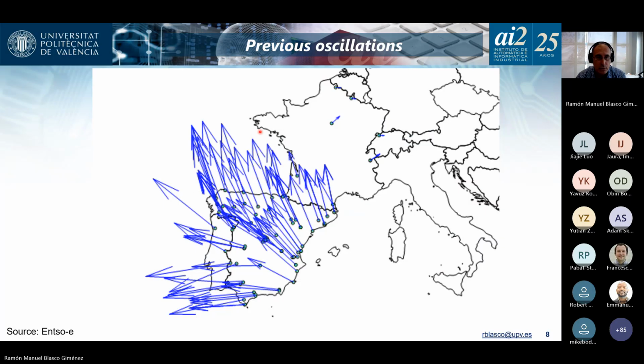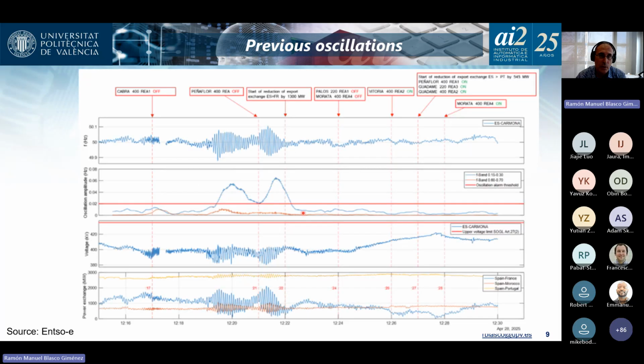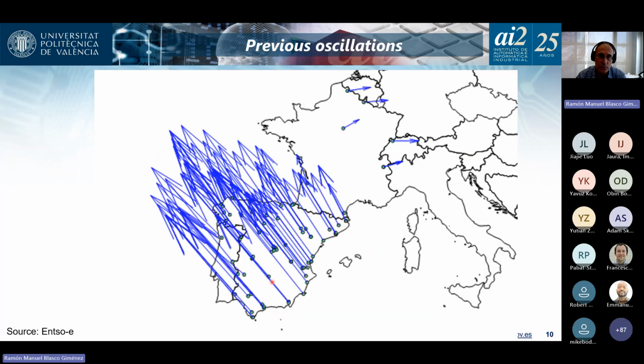If you see these oscillations, the 0.6 hertz, clearly the generators in the north of Spain were oscillating against generation in the north. So this was the internal oscillation that I was showing before. But as well as the internal oscillation, we had other oscillations between Spain and the rest of Europe. You see that all generators in Spain were oscillating with the same amplitude and angle against the generators in the rest of Europe.